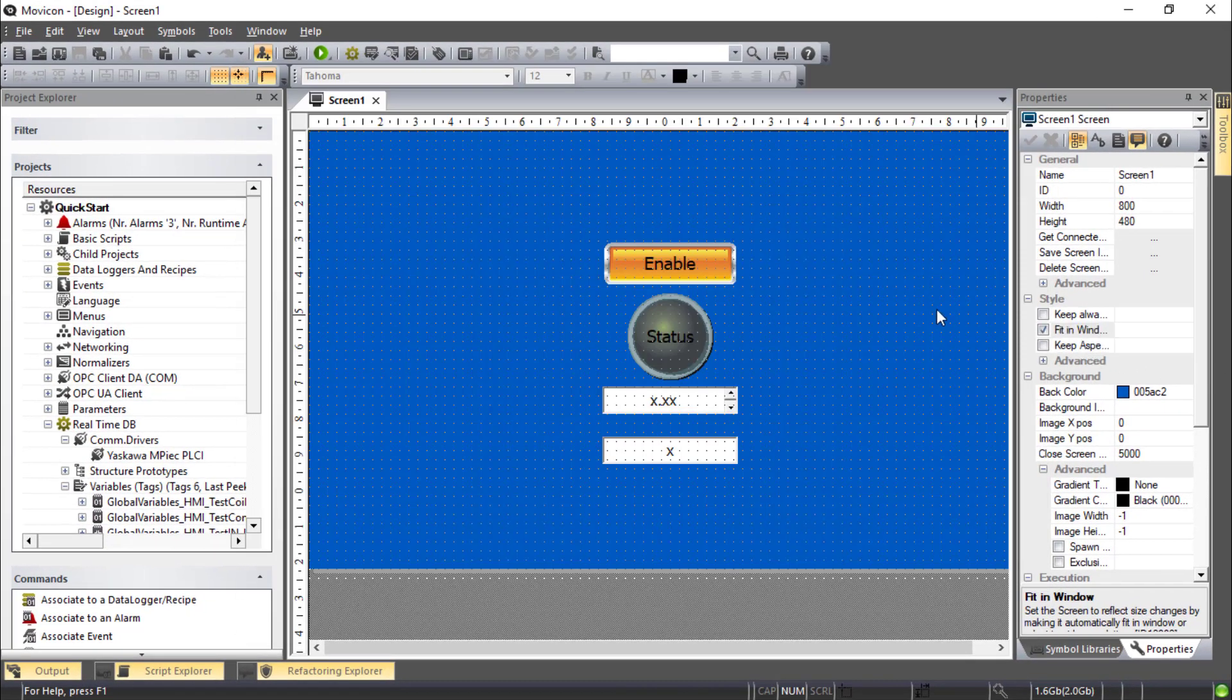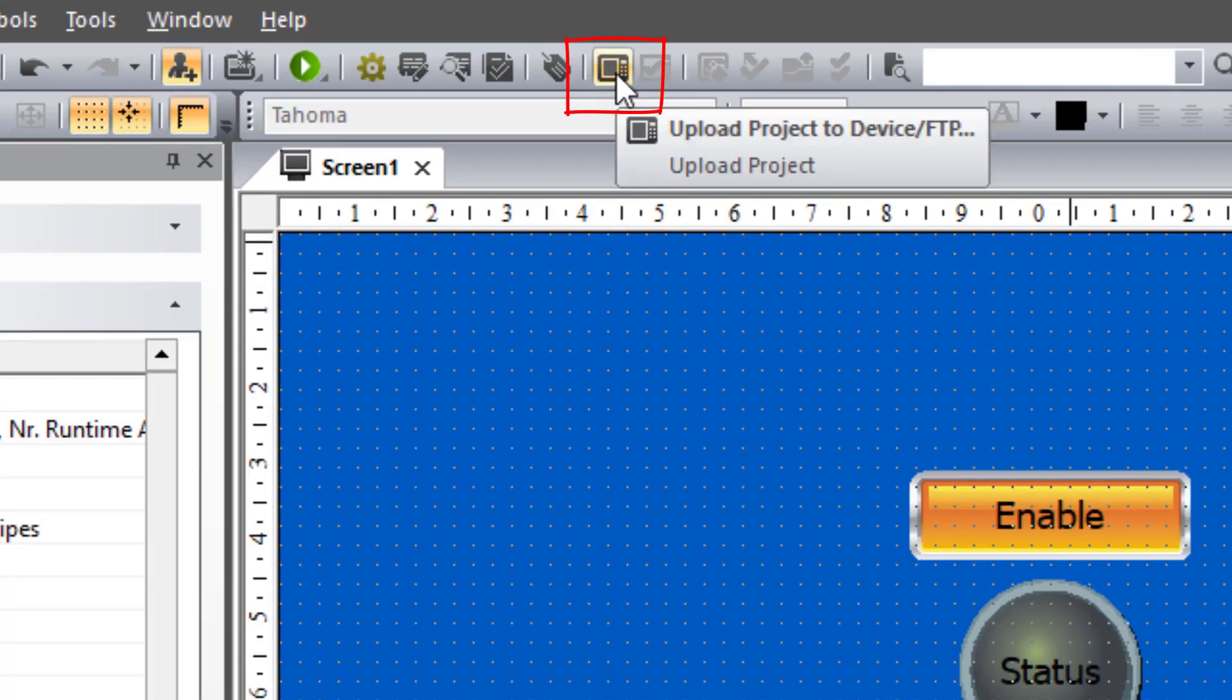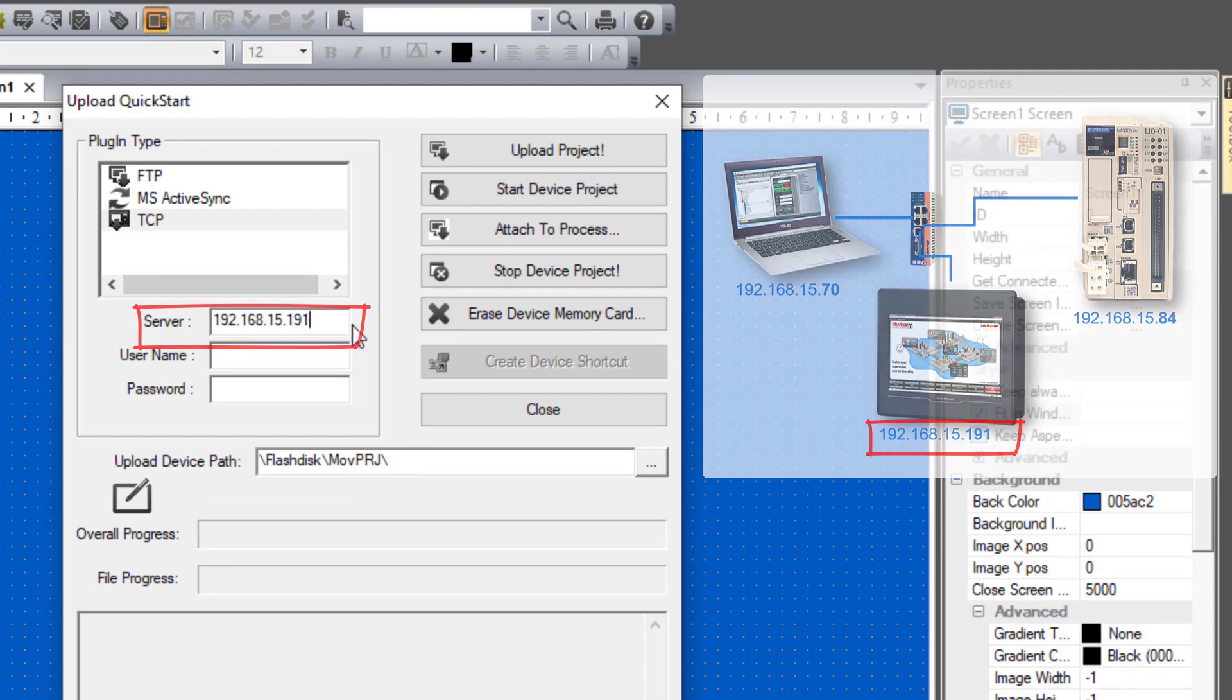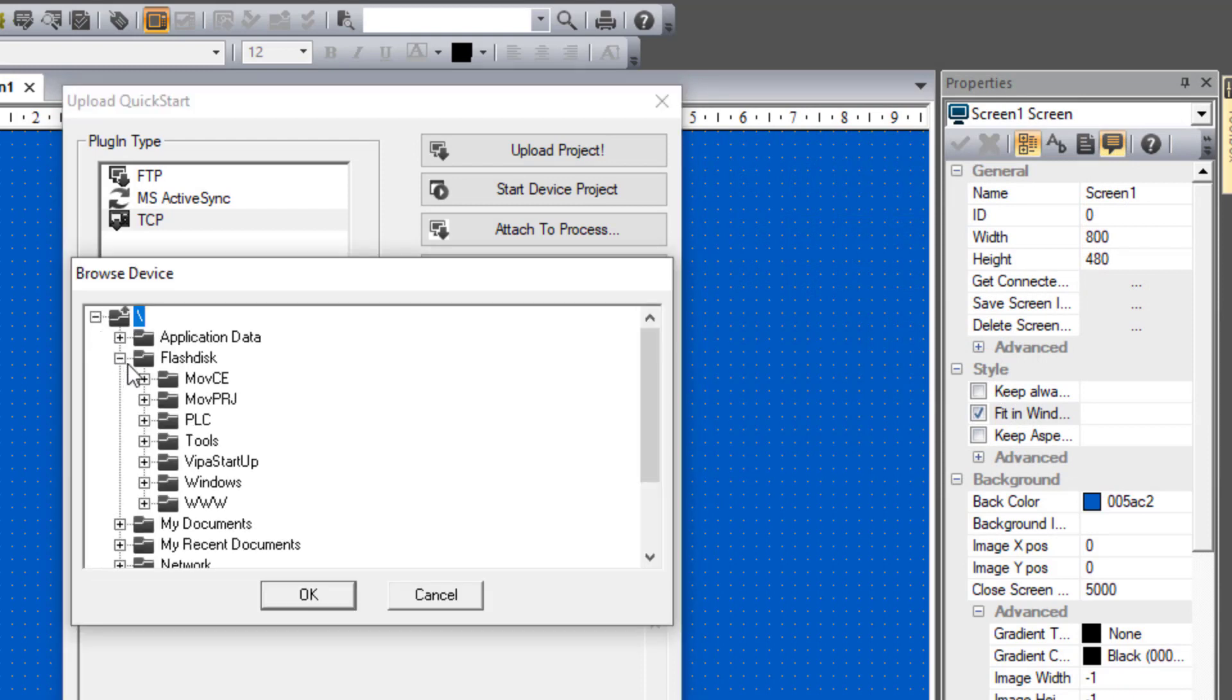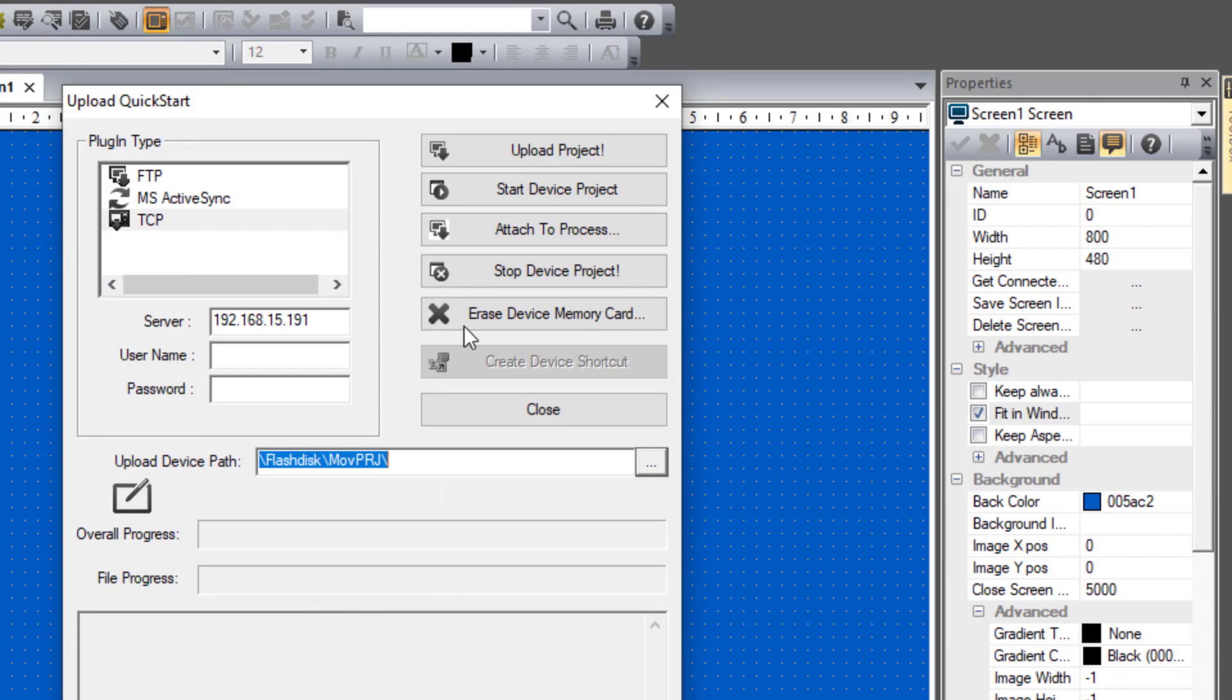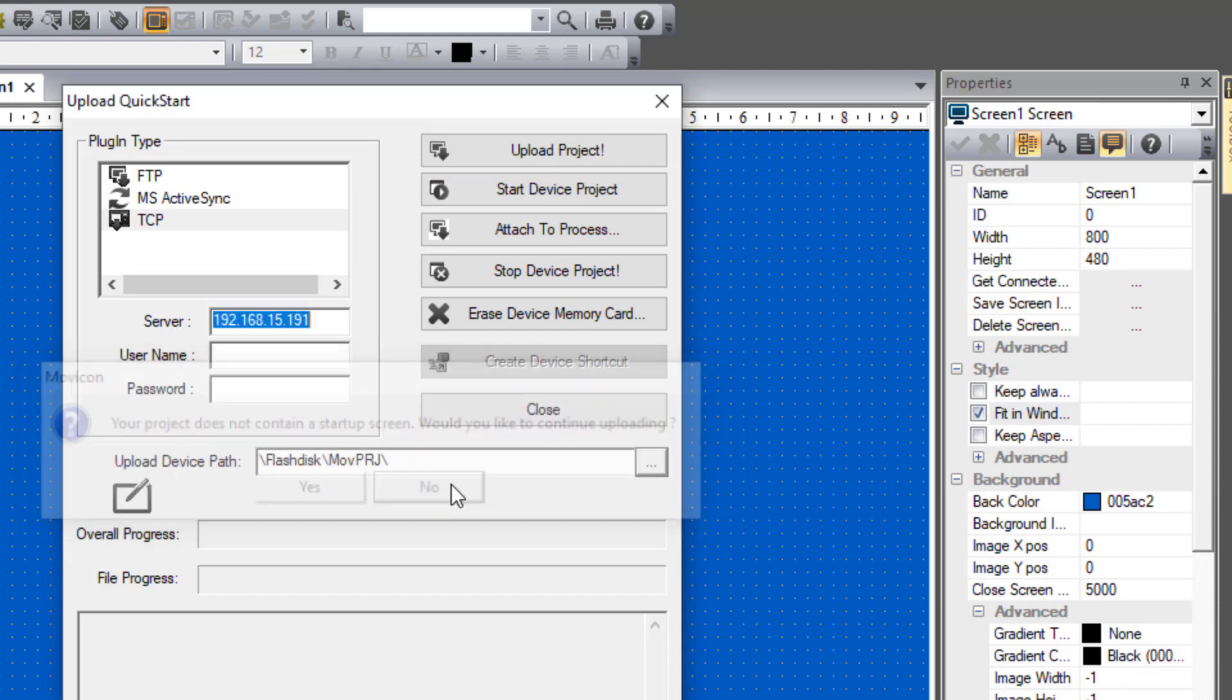So back in Movicon. Go to this icon called Upload Project to Device. You set the server to the IP address of the HMI. I'll also take a look at the Upload Device Path. And you can browse to find the flash disk MOVPRJ folder. Or really any folder will do. And click Upload Project. Now there's warning about there being no startup screen. And that's easy enough to fix. So click No to stop uploading. We'll close it.